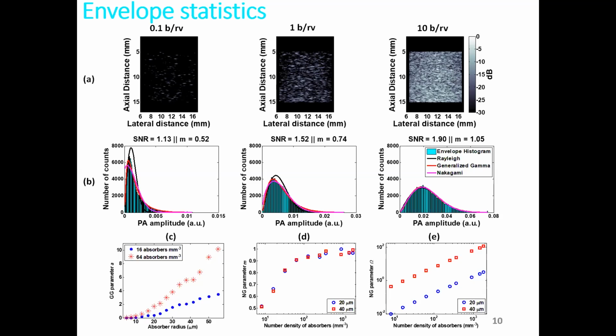And at that point, you might want to consider other types of approaches where you are using phantoms with blood, with whole blood or oxy or deoxy blood. So where you're now looking at vessels of sizes that you can control and make them as small or as large as you need to mimic the, say, vasculature of whatever it is that you will be studying.